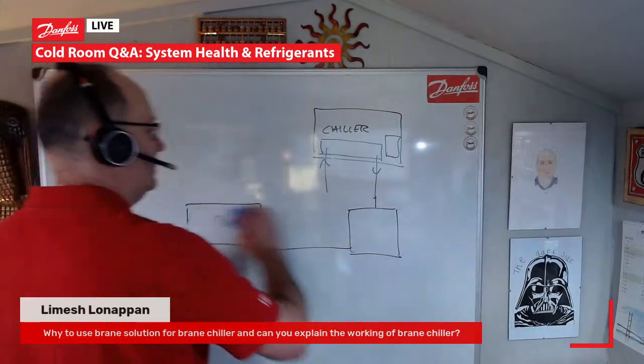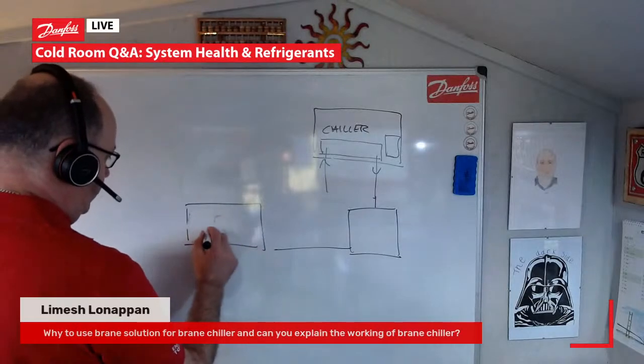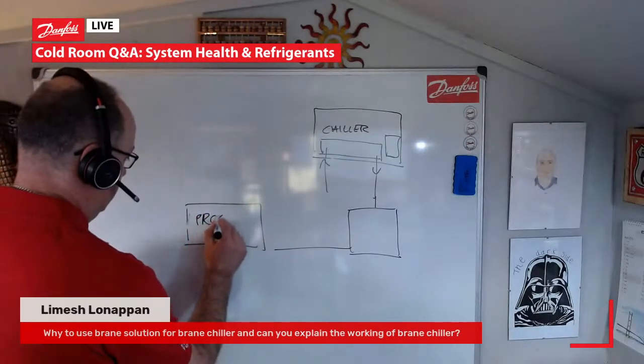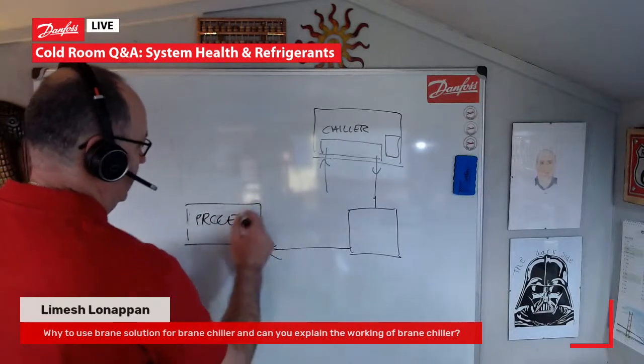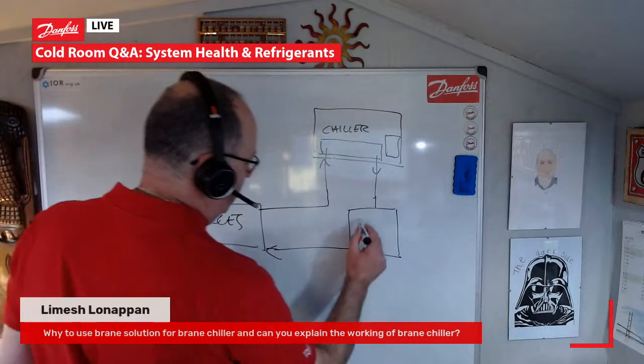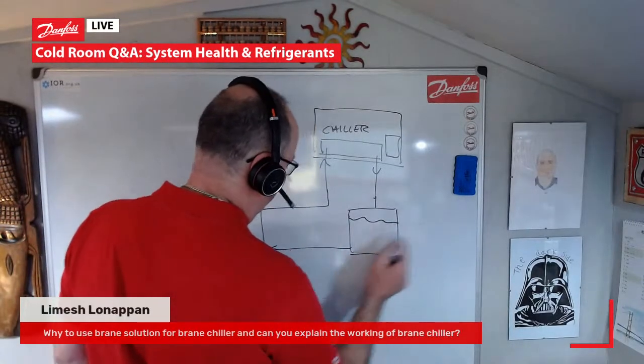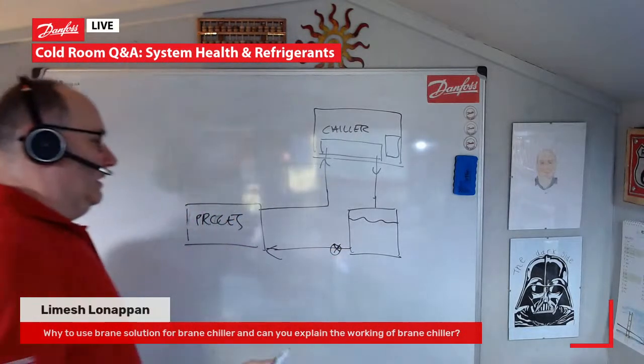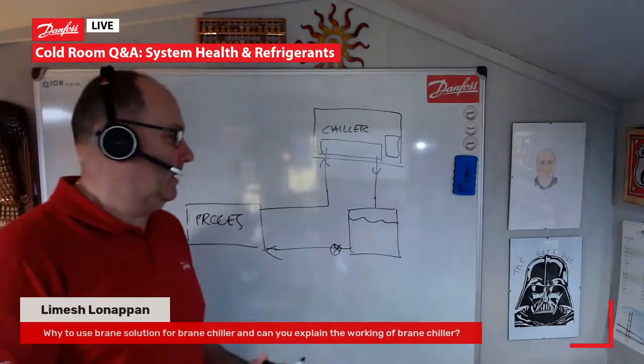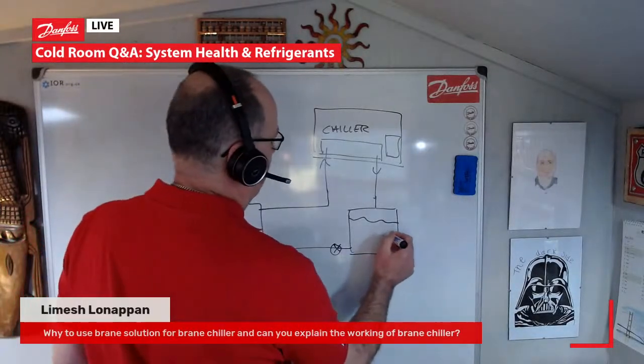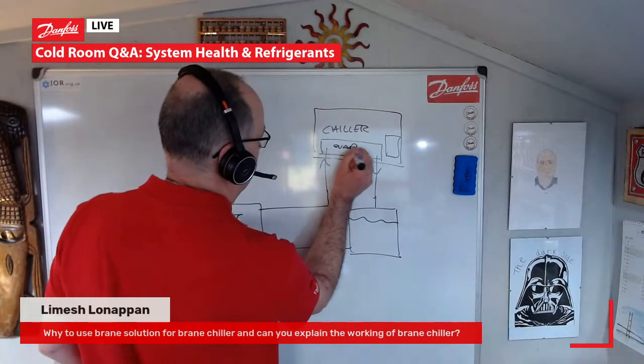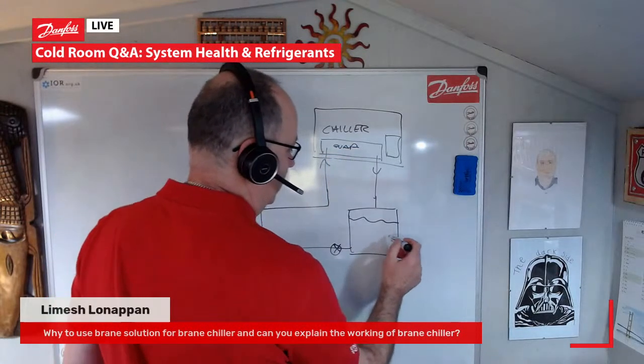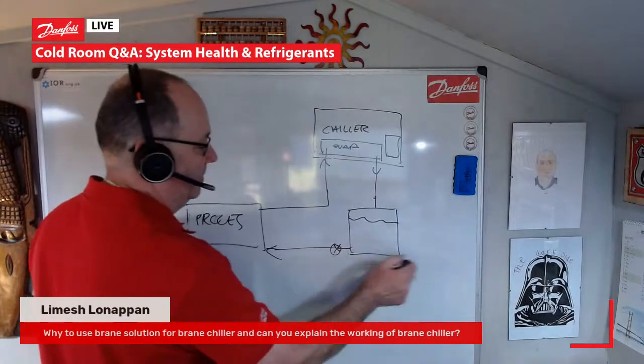How do we show that? And then we'll come back out of the process, back through the chiller, and that tank will maintain a level. We'll have a pump. That's in its very basic format. The main thing we've got to be careful of is our evaporating temperature here, and the consistency of the brine, the specific gravity of the brine, so we don't freeze the brine. And you can find there are various charts that will tell you the specific gravity of the brine that you need so you don't freeze it.